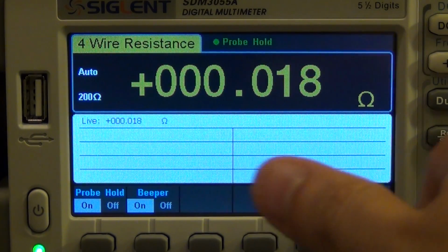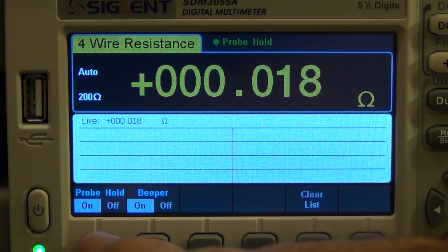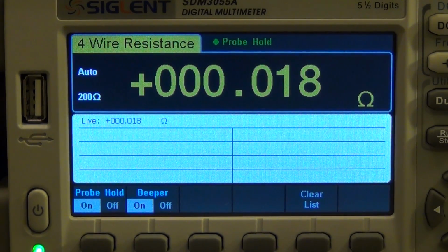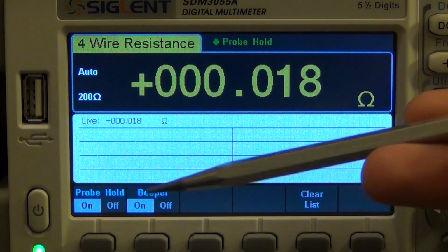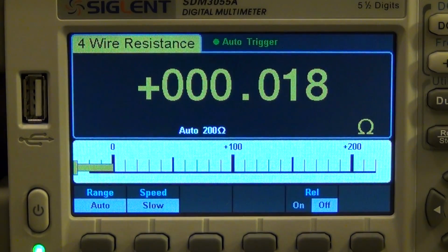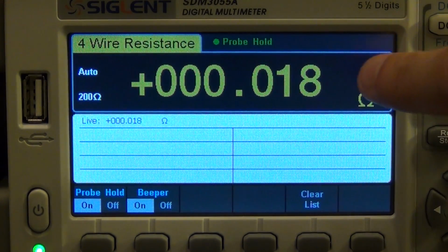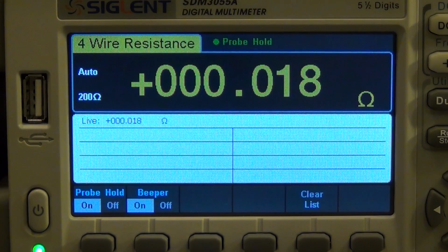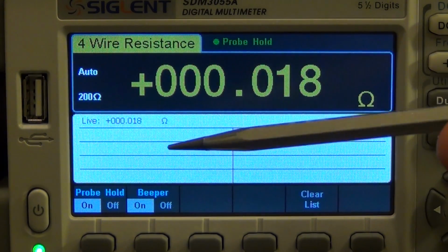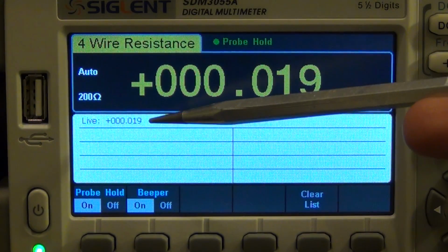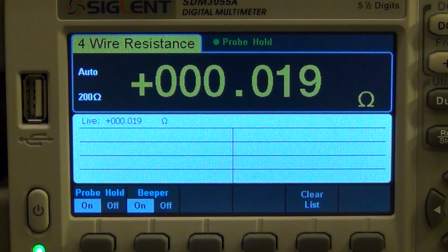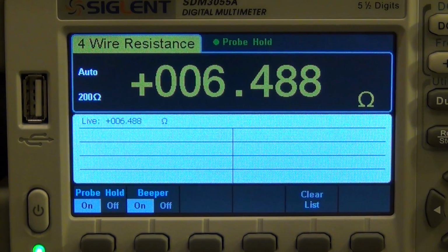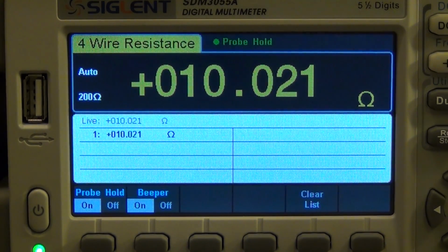So let's go ahead, and I've already enabled it. I'm already under the hold menu here. You can see that I have the hold here, and the instrument says that the probe hold is on, and if I turn it off just like that, it will just go back to the histogram measurement we had. So I'm going to enable it again, and the beeper is on. Now it is measuring continuously in the background, but it will only detect a new measurement once it feels like a new measurement has changed sufficiently that it would be considered a new unit to be recorded. So you can see the live value is shown over there at the very top. I like that. Let's go and give it 10 ohms. There we go. You can see that it detected that as a new measurement, and it added it to our list.